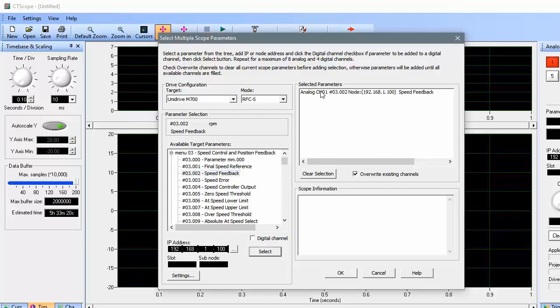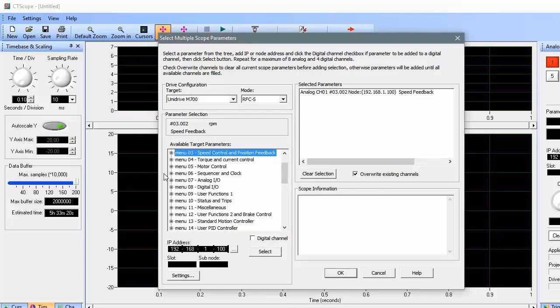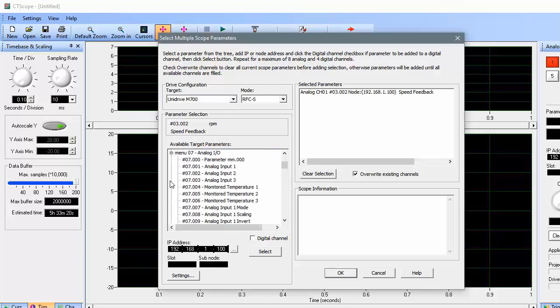On channel 2, I'm going to look at my speed reference, which in this case is an analog signal that's connected to analog input number 1 on my drive. The analog parameters are located in menu 7, so I'll expand menu 7 and then choose parameter number 1 for my second channel.